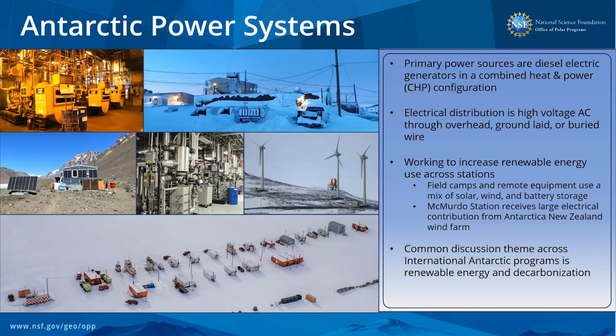At McMurdo Station, we operate that grid in conjunction with Antarctica New Zealand. One side of the grid is the Antarctica New Zealand station, which operates on 50 hertz power, and the other end is McMurdo Station operating on 60 hertz power. In the middle, Antarctica New Zealand operates 3 wind turbines, which give us a pretty good contribution of our power.